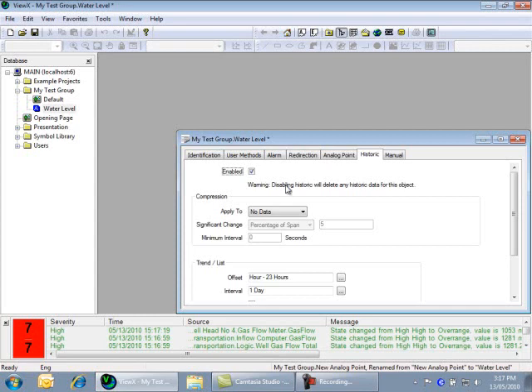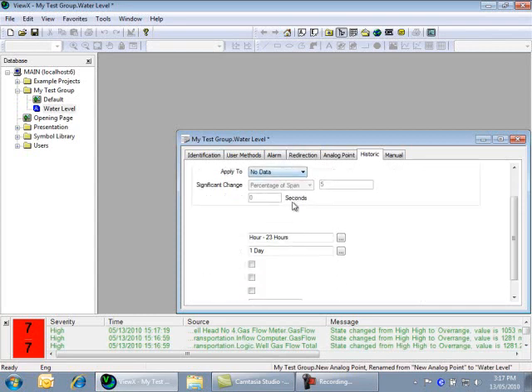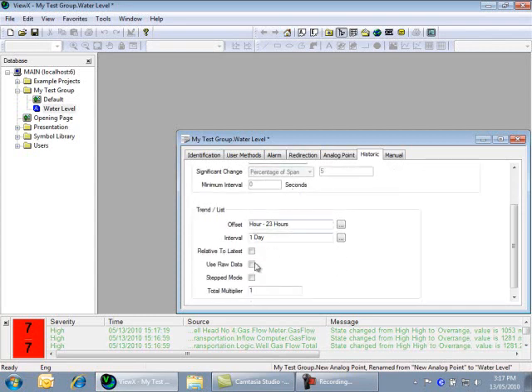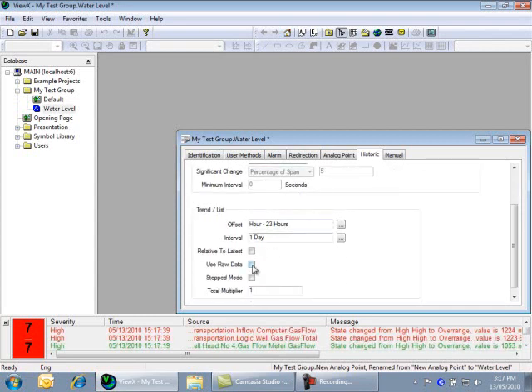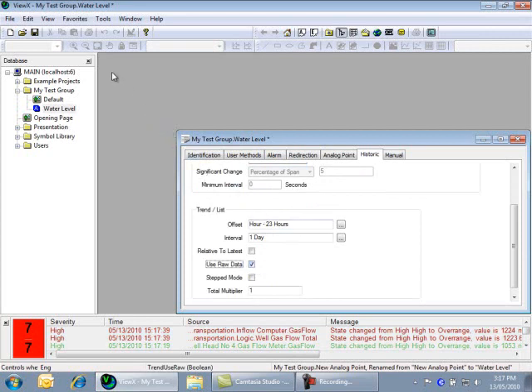ClearSCADA will now send any point value changes for our water level point to the built-in historian for future reference, trending, reporting, or archiving. At the bottom of the same tab, select the option to Use Raw Data. Save the Properties form by clicking on the Save icon in the toolbar, and close the Properties form.